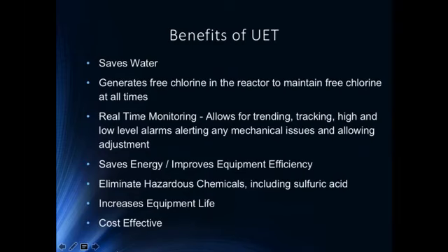Eliminating hazardous chemicals. In the Southern California area, because water quality is such a big deal, sustainability, saving water, there are properties that have used sulfuric acid or side stream softening for many years to save a little bit more water. Typically, you only get another cycle or two, but essentially at that point, you're introducing a much more hazardous chemical, or from a softener standpoint, you're adding a lot of salt to the system. It's a very high maintenance issue. So we're able to do that without any of these ancillary chemicals.